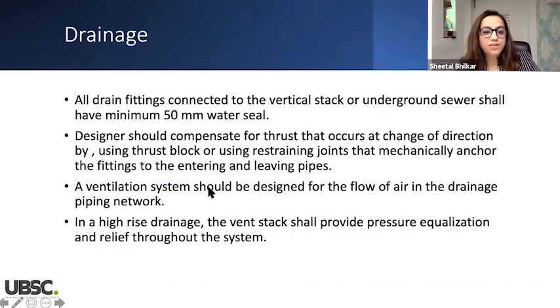Even in drainage, when you are designing drainage, you have to make sure that all drain fittings connected to the vertical stack or underground sewer should have a minimum 50 mm water seal. Also, the designer should compensate for thrust that occurs at a change of direction in the pipes, where thrust blocks and restraining joints should be used that mechanically anchor the fittings to the entering and leaving pipes. So that care should be taken.